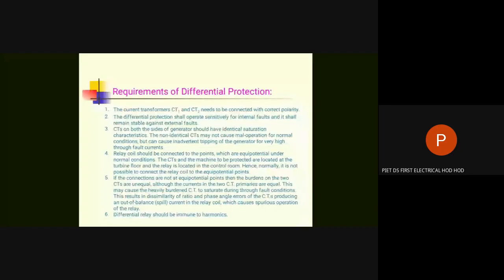under normal condition the CTs are working in the linear region of their saturation characteristic. But when the external fault occurs, the CTs are giving different open circuit voltages, and therefore they are injecting different currents, small I1 and small I2, and I1 minus I2, that is the difference of current, will be present, and this can mal-operate the relay because there is no internal fault. To take care of this condition, we have to connect a resistance in series with the relay, and that resistance is known as stabilizing resistance, because two exactly identical CTs are never possible.